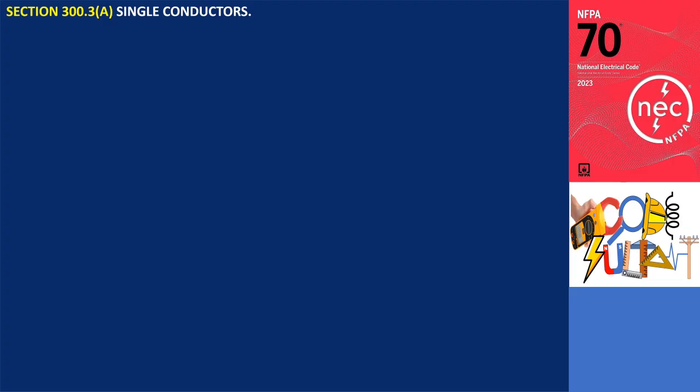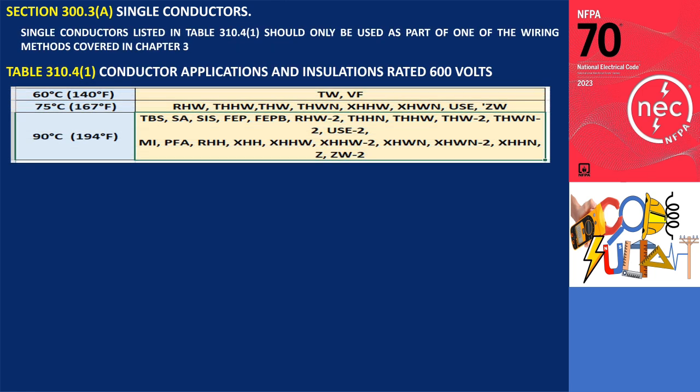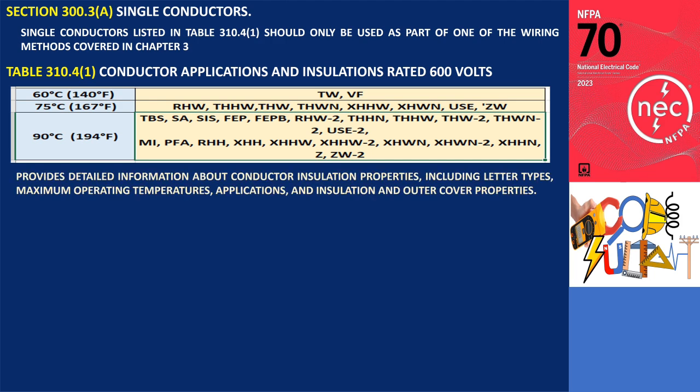Section 300.3a specifies that the single conductors listed in Table 310.4.1 should only be used as part of one of the wiring methods covered in Chapter 3. Table 310.4.1 provides detailed information about conductor insulation properties, including letter types, maximum operating temperatures, applications, and insulation and outer cover properties.